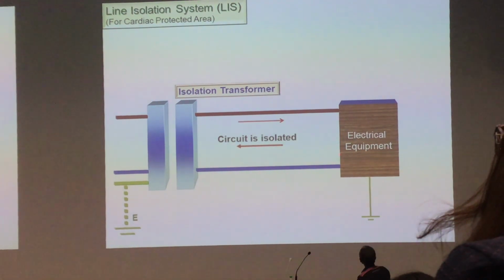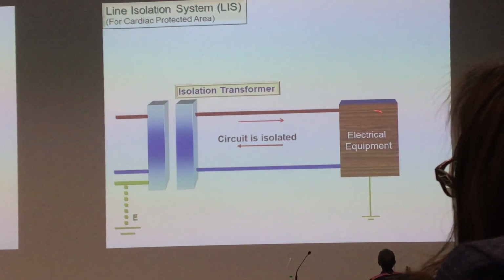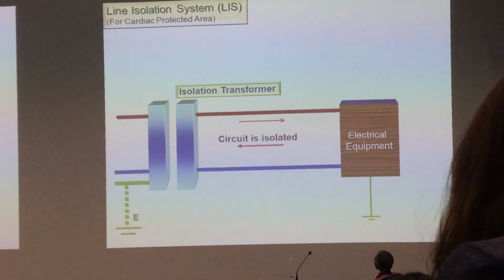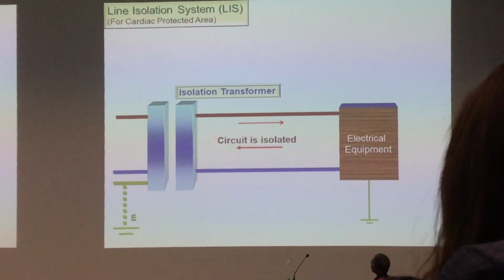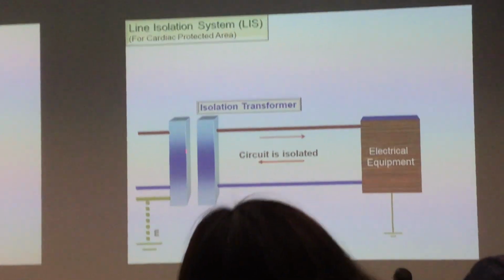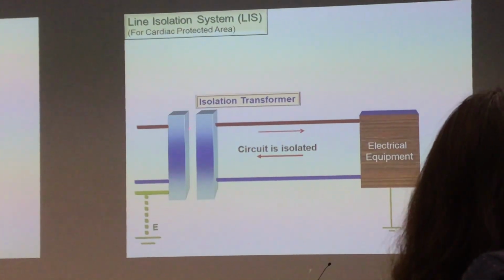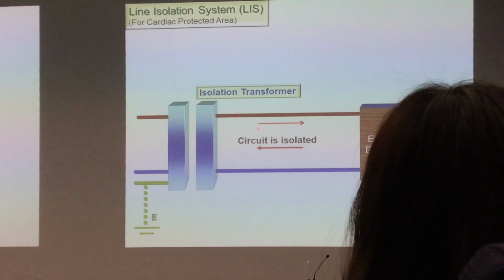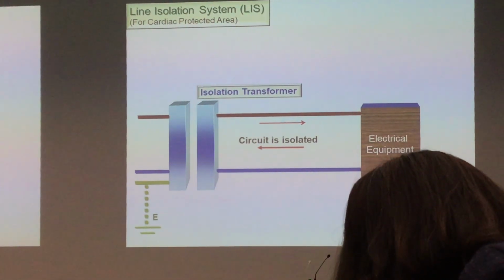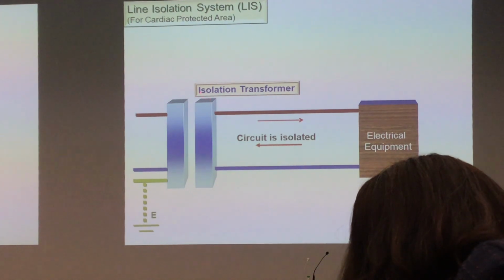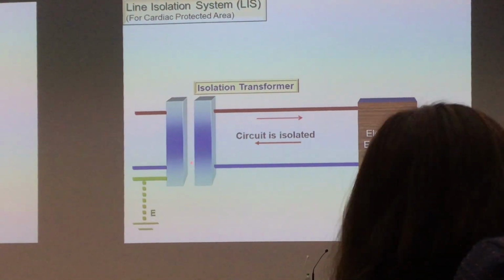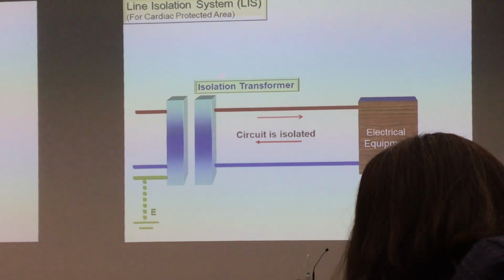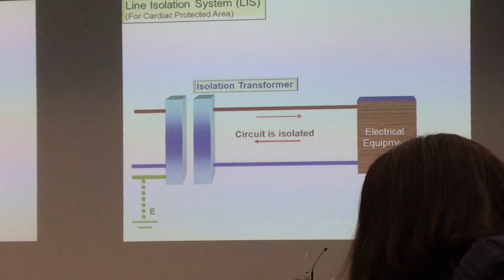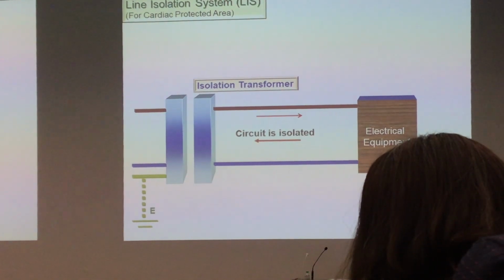Basically, this is your machine, for example, and this is the power supply. There's an isolation transformer which separates these two systems. There's no direct connection between supply and equipment; these two are separated by a transformer called an isolation transformer. Which means this circuit is 100% independent from the supply. That's why they call it an isolation transformer, or line isolation system, LIS, or line isolation monitor.